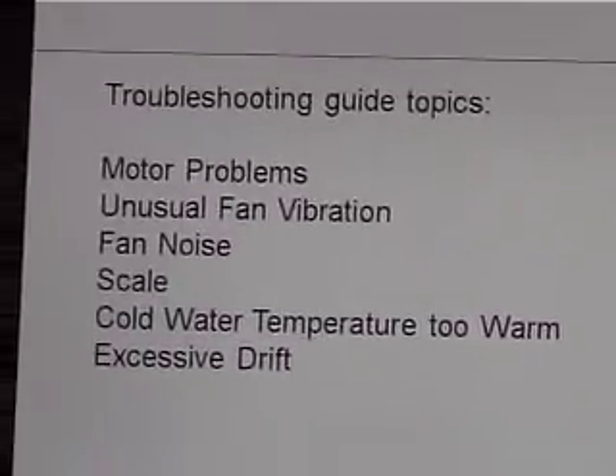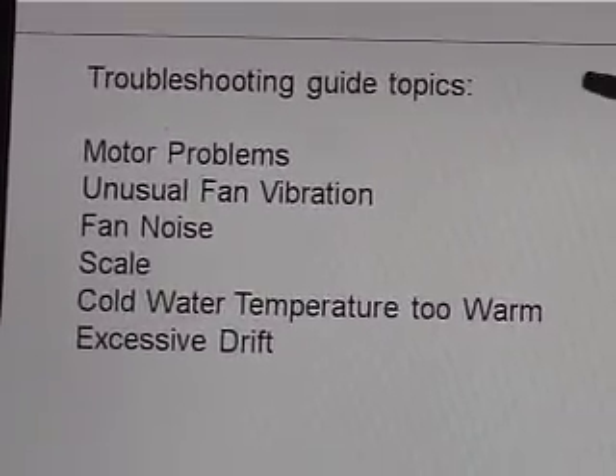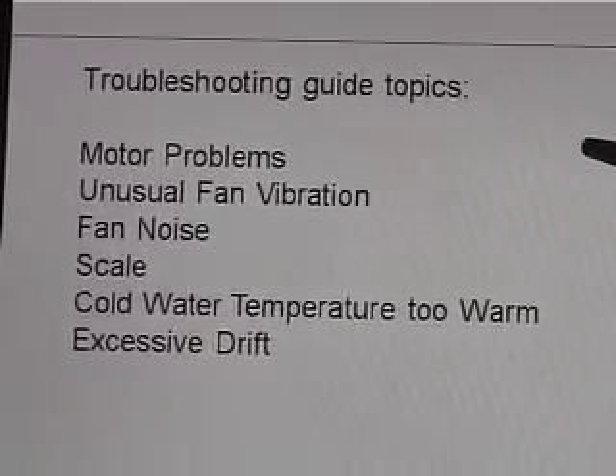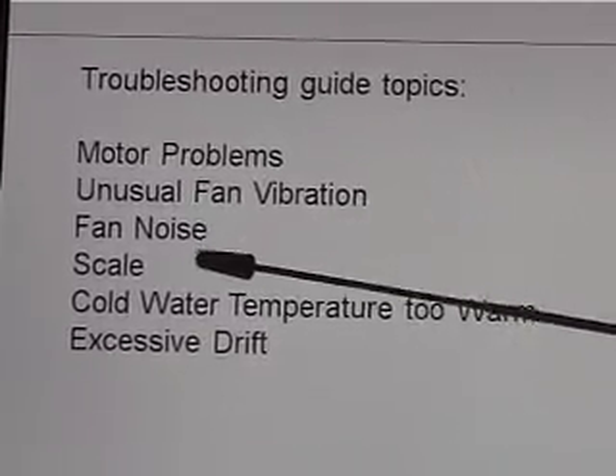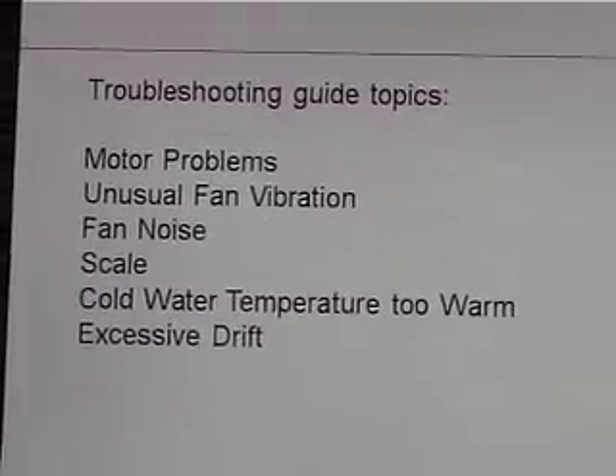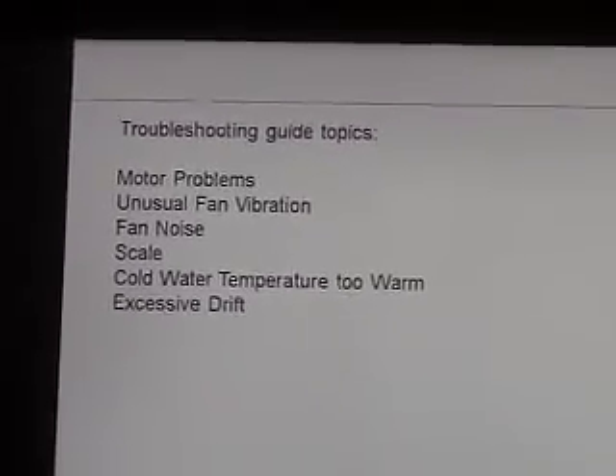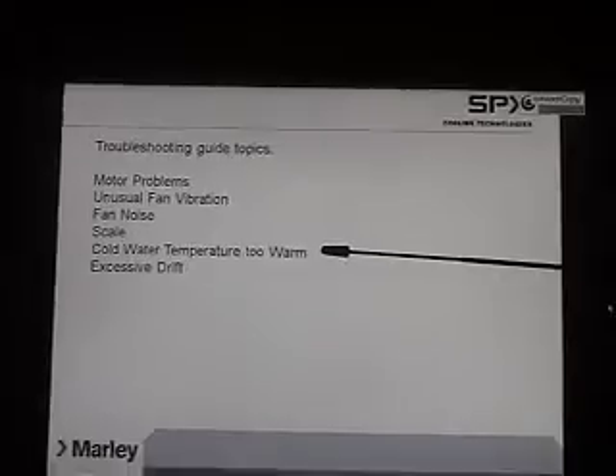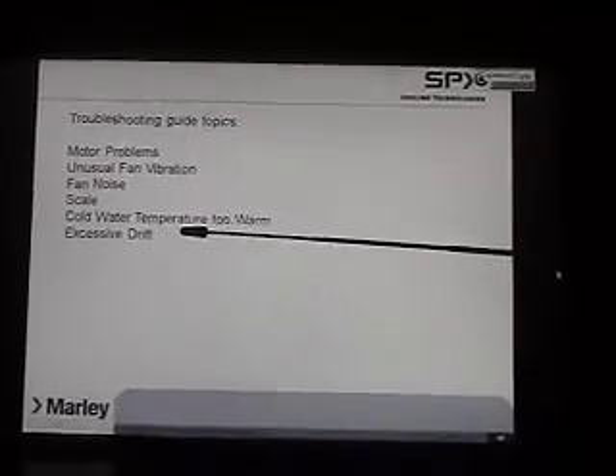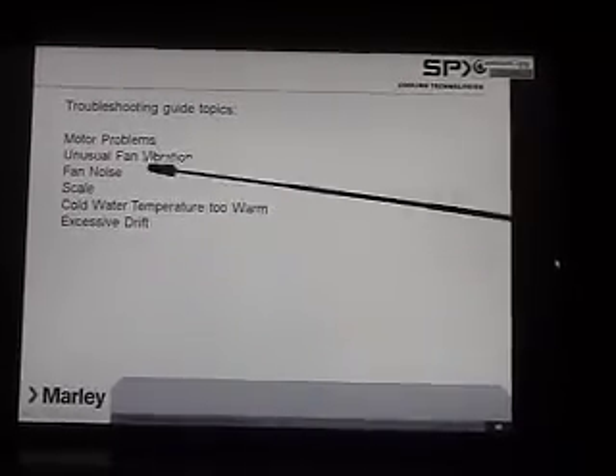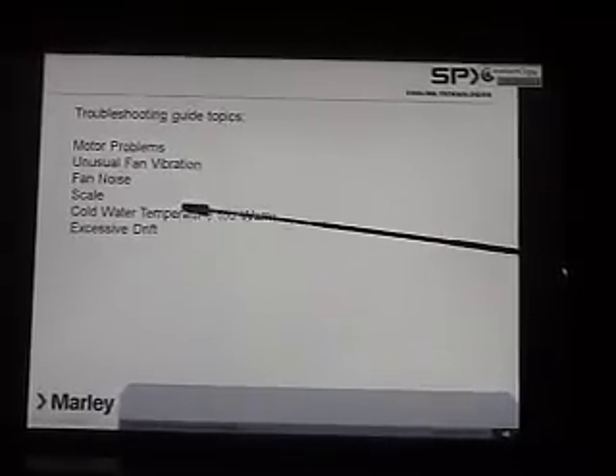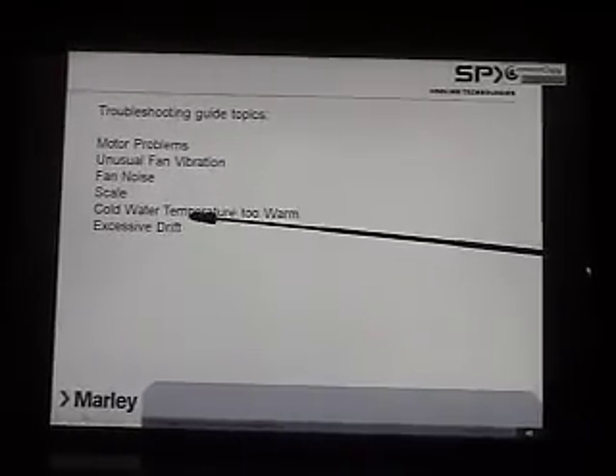There's a troubleshooting guide on the last page of the user manual on page 38 and 39. It covers in depth various motor problems, unusual fan vibration, fan noise, again scaling, which is proper water treatment. You know, what are some of the things you can do if the water temperature is too warm, and then excessive drift, which would most likely be a hole in your drift eliminators, or maybe they're not quite wedged in right.